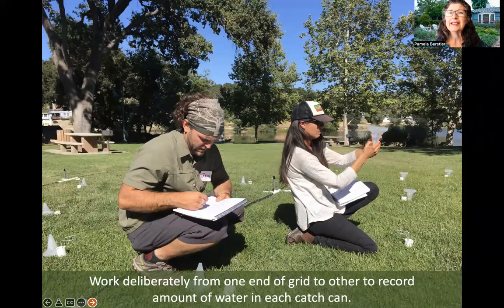And then the last part is to gather the data. This is another place where it's really nice to have a second person to help you. What you do want to make sure is if there is more than one person, that it's the same person who reads the cans each time. Otherwise, they can be interpreted a little bit differently. And then you just want to work really slowly, deliberately, and logically. So you start at catch can 1, you read the amount, you record it. We actually recommend recording it on the drawing and then transferring it later. For me, it's just a way of double checking that I am capturing the information for the correct catch can.